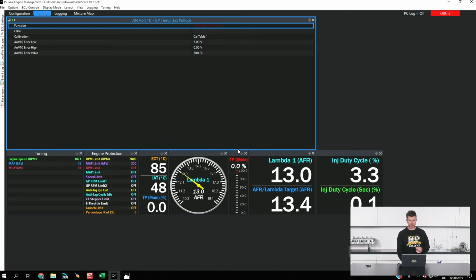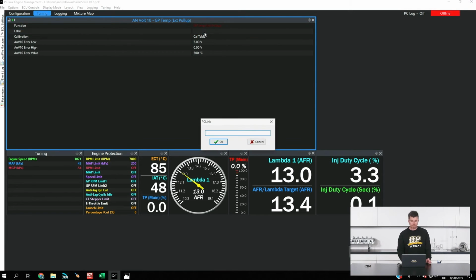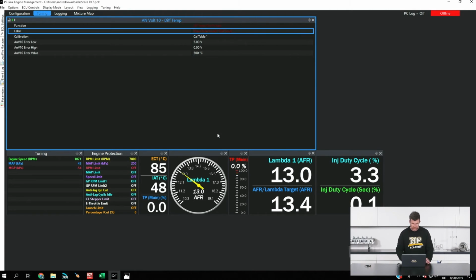So let's set up a general purpose temp sensor. We can give this a label so that we know what that's going to be - let's call this diff temp. That'll probably be fine. And then we've got exactly the same situation here. We've got our calibration that we're going to be using, in this case cal table 1. In this case, because it is an analog voltage input, we are going to be doing that calibration in terms of voltage.